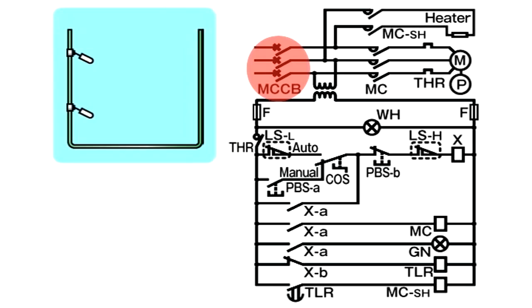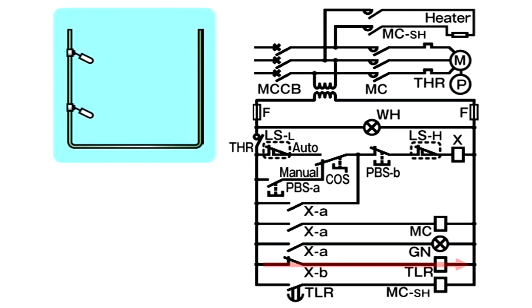The MCC-B is turned on. As voltage is applied to the sequence circuit through the transformer, the white lamp WH illuminates, current is passed through XB, exciting the coil of the on-delay timer TLR. TLR's relay operates if no operation is carried out from the time of execution until a set time has elapsed.